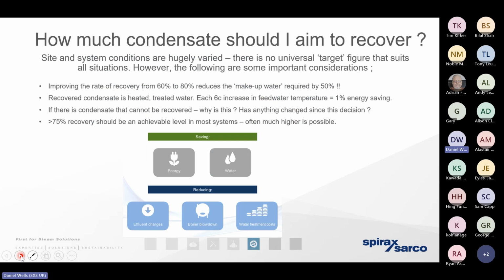Again, we don't know. Another rule of thumb would be if we could recover 85% of our condensate and get it to the boiler house at a temperature of 85 degrees, that'd be a pretty good target to aspire to. But it reminds us that if we can recover as much of the condensate as we possibly can, we're going to have a significant and proven benefit in terms of how we've now optimized our steam system.